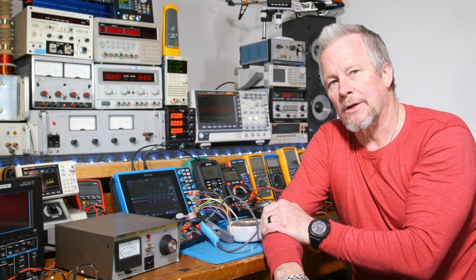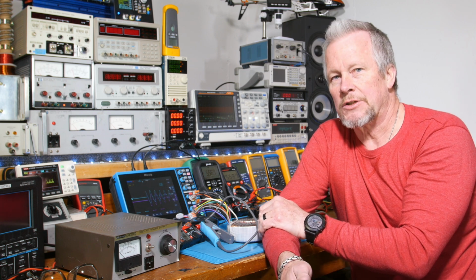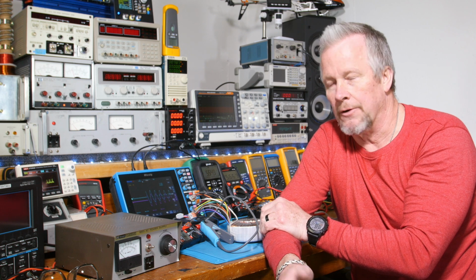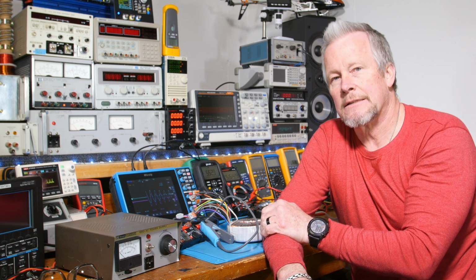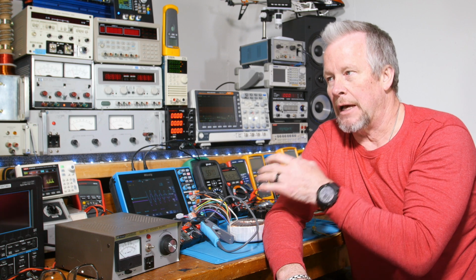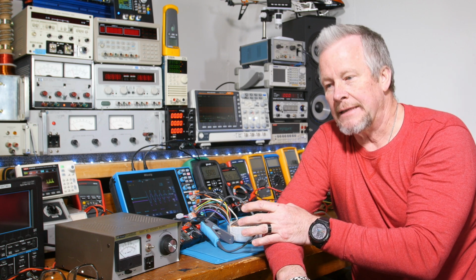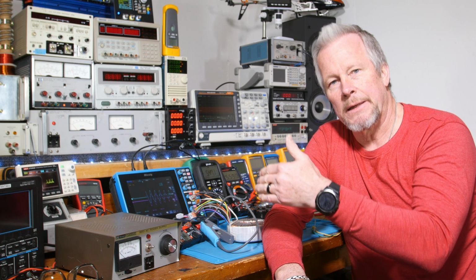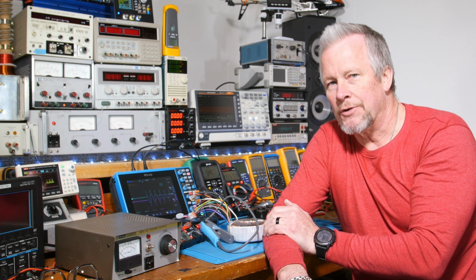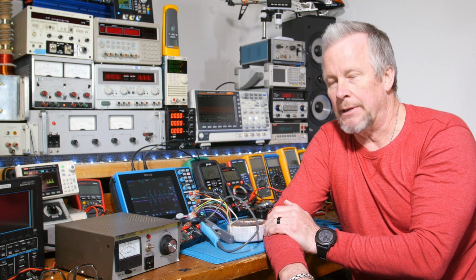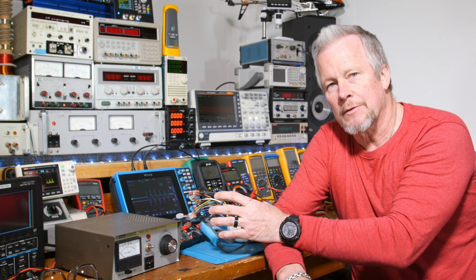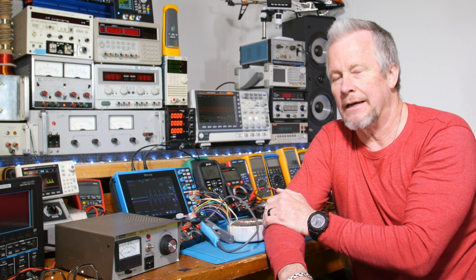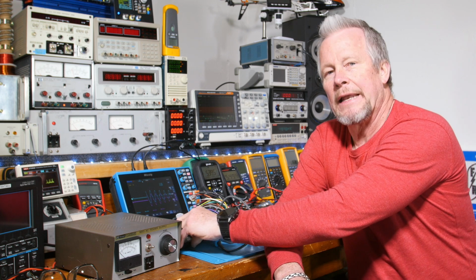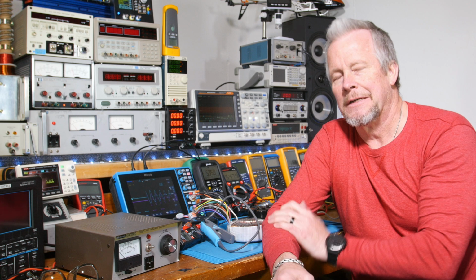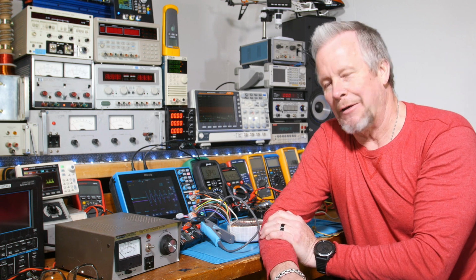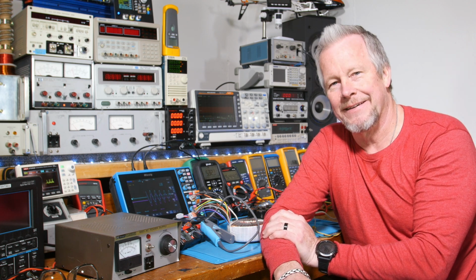When you pick out breakers, you can get ones that have inrush control, but even if they don't, they're still slow. I think 100 milliseconds is kind of a standard thing, a lot of fans, when they kick on, it takes so many cycles for them to spin up, usually more like 200 or 300 milliseconds before they spin up. So if it's capturing the first 100 milliseconds, it's capturing the worst of that. I just wanted to point that out, that's why I put that into the test, just to make that point. A little extra learning thing.